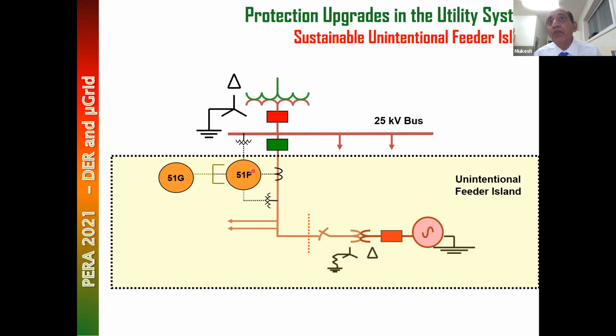So when we put a modern protection here, it's a microprocessor based relay, which has three-phase protection and ground protection. Typically we don't have a potential transformer here on a distribution feeder because it's a unidirectional flow of power. We don't need a PT in a normal distribution feeder, but once we put a source here, and if this source can form a microgrid, then we need a PT here to allow synchronizing or sync check closing. If there's a source here, you can't close this breaker without having the two sides of the system synchronized. So we have to add a PT here for a sustainable island, and we have to put a modern protection here. These are the optimizations we do based on the 2:1 rule. If the feeder island is sustainable, we need to add this.